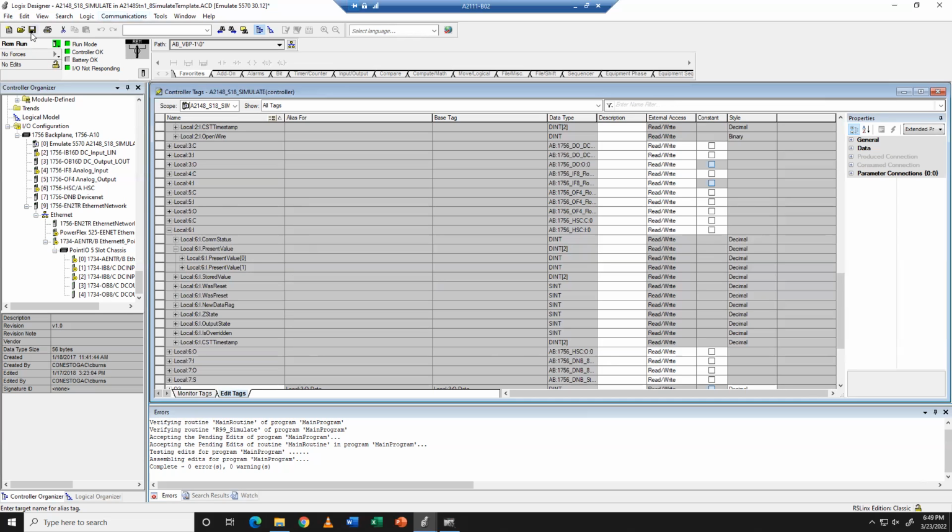If you ever need an SLC PLC to read information from a Logix 5000 controller, because the Logix 5000 controllers use tag-based addressing and the SLCs use register-based addressing, they don't speak the same language. They both use the same CIP protocol, so they can transfer data from one another. But it's far easier for the 5000 to read from the SLC.